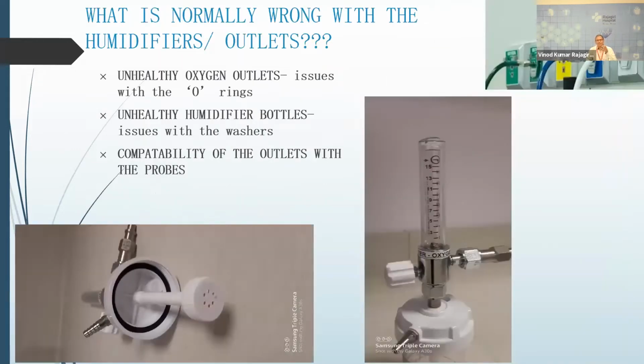Now, there is something else to talk about. What are these humidifiers and the outlets at the different beds inside the critical areas? Something is always missing at these points, and they become unhealthy. Why? Because there are parts in these humidifiers and outlets which are not really looked at because of improper maintenance. You have to look at issues with the O-rings and issues with the washers, and do preventive maintenance to ensure that the leakages from these outlets and humidifier bottles are controlled, minimized or even reduced by proper handling. Well-trained people handling these probes on the outlets is also important when it comes to the bedside units when they provide oxygen to patients.